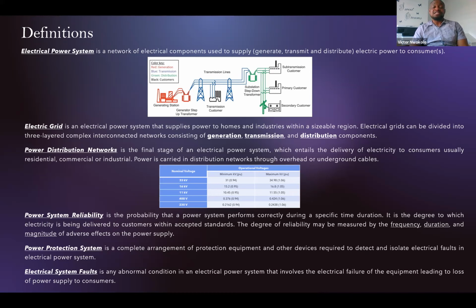In other countries, this varies. Like in the industrial setup, it varies as well. Like an industrial setup, low voltage is primarily for distribution, except for where we've got some high voltage consumers like export pumps and some VSDs that operate at around 3.3 kV, 6.6 kV. These are specialist loads. So in the Nigerian context, it ranges from 230 volts single phase to 33 kV high voltage three phase. Then in the course of our discussion, we'll be looking at power system reliability, and this is basically the probability that a power system performs correctly during a specific time duration.